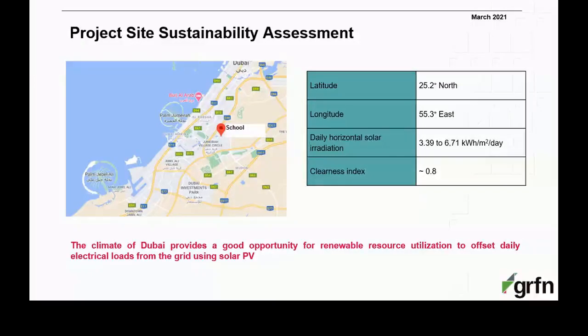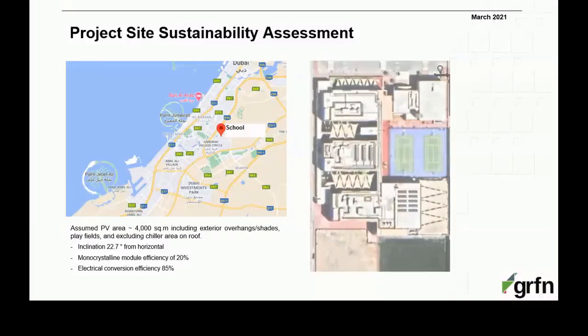Now, looking at the site, we looked at the location, obviously, to get the amount of available solar radiation. We know that Dubai has a lot of potential for solar, and we looked at the amount of usable area. It's around 4,000 square meters that we can use on that school. Excluding the chiller yard area, most of the other areas can be used to install PVs. The assumption here is an inclination of around 23 degrees, and the efficiency of the module is around 20%.